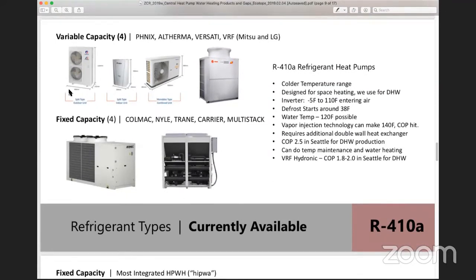There were reasons why we did that. One was there were existing tanks there, and they had an original electric boiler, so that set the constraint. But anyway, getting into this, I'll start by reviewing what's out there. In the 410A equipment, none of it's really designed specifically for hot water. So we've been using these systems with double wall heat exchangers and making hot water. In our climate, we can make 120 just about year round until we get into the 30s outdoors, and then we're usually limited on temp. Some technologies like VRF will actually limit the output to about 108, so they won't even guarantee 120. But the key here is that the 410A equipment right now is mostly space heating.